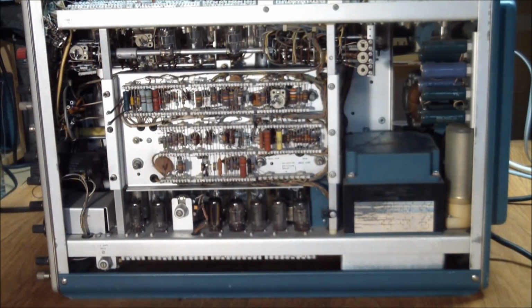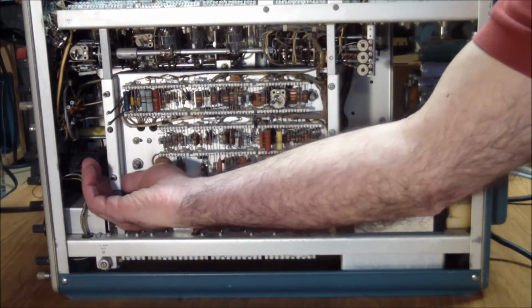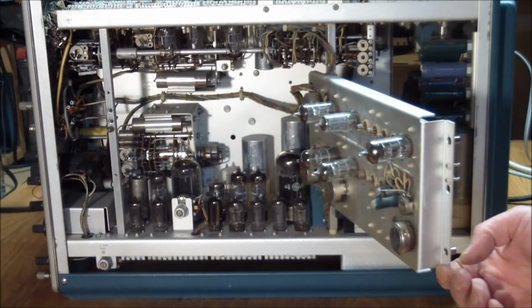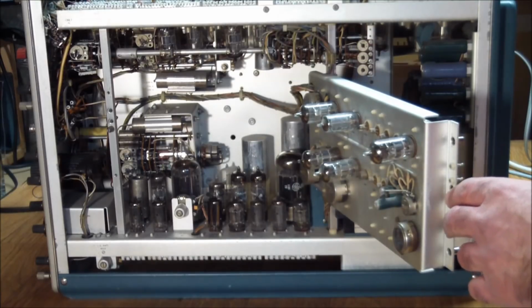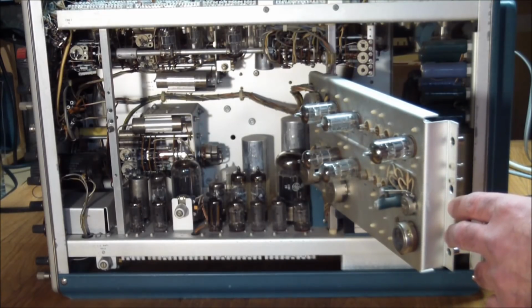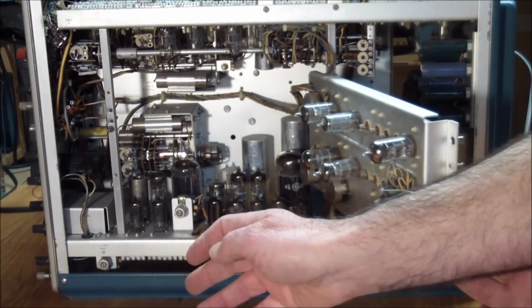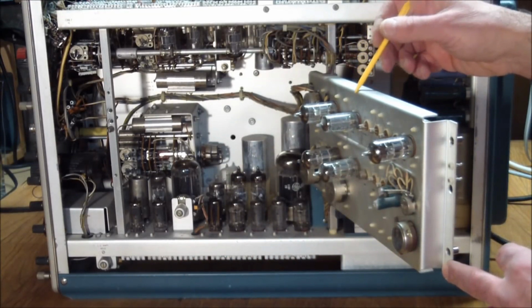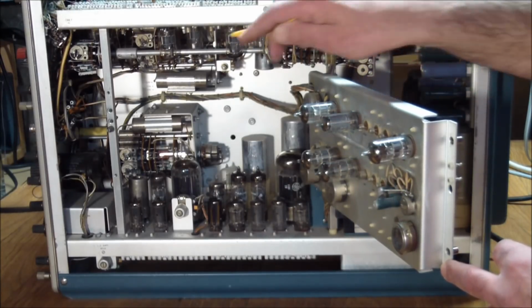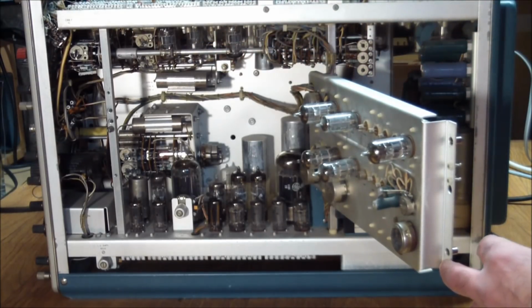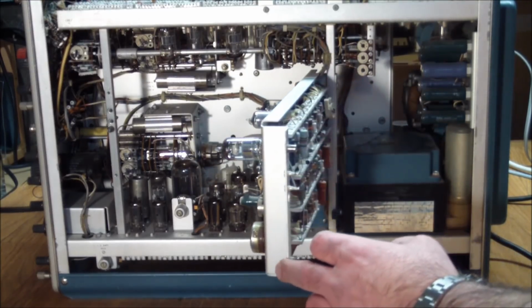Well, some time has passed, and during that I pulled all of the tubes, cleaned the pins, and stuck them into the tube tester. You're looking at the left side of the instrument, and one of the nice things they did here is that this whole panel swings open, giving you access to everything. As you can see, there's the tube complement both on the bottom of the chassis as well as on the back side of the swing out chassis, and also on top over here.